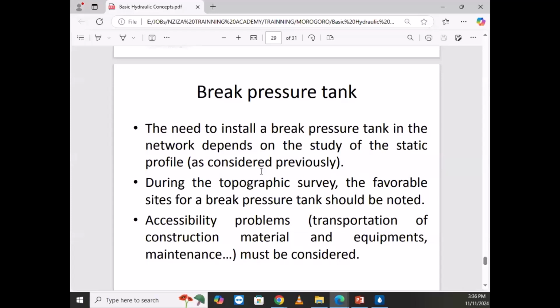But I really know that by putting the tank here, this will require you high pipes, a big pipe, because they will require most energy to climb this pipe. But by breaking here, the water with the force here will have much pressure to reach this place, and then it goes down. So you just play with those calculations. You see, in the model, it's very easy. It's just a matter of putting the tank, removing the tank, putting the tank, removing the tank. You see the scenario.